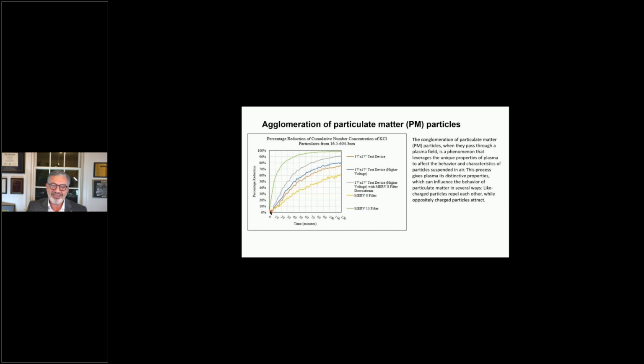This would be a MERV8. This would be a MERV13. This is the non-thermal plasma system. And then when you combine it with a MERV8, you see this kind of a response. So like what we saw earlier, as these ions are floating around, you create an agglomeration that occurs of these submicron particles or ultrafines. And this doesn't only occur with non-thermal plasma, but ionization and bipolar ionization, like needlepoint ionization with bipolar ionization, does the same thing, which is a fabulous phenomena that occurs.